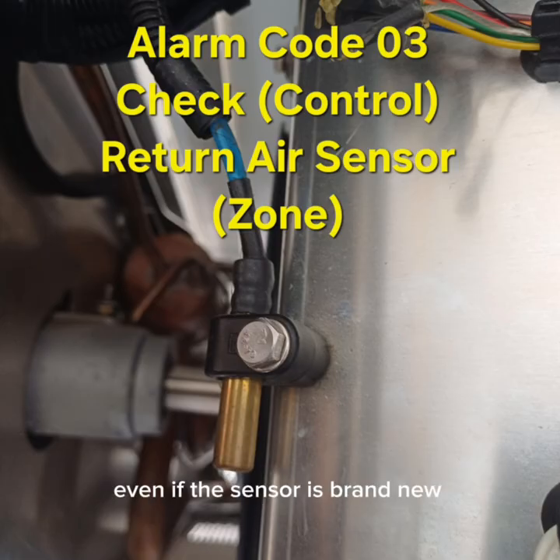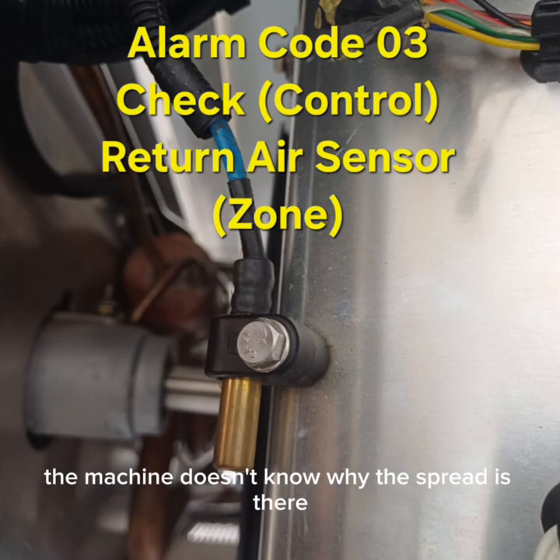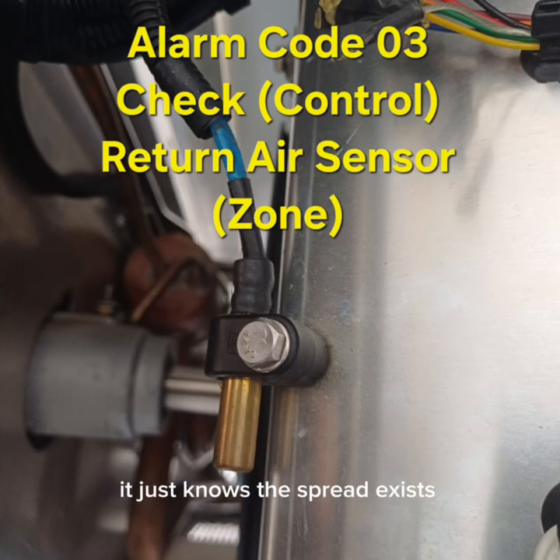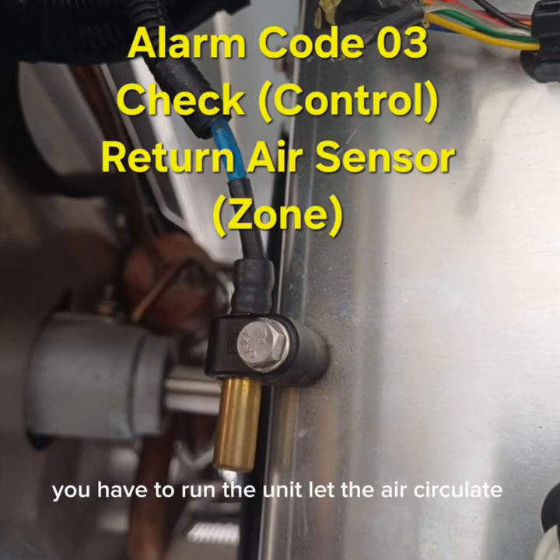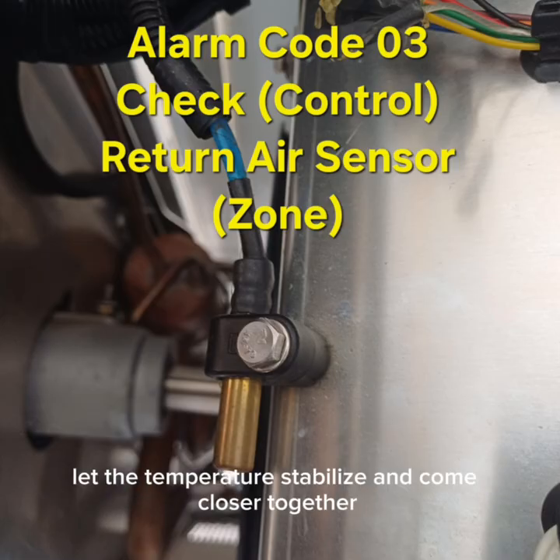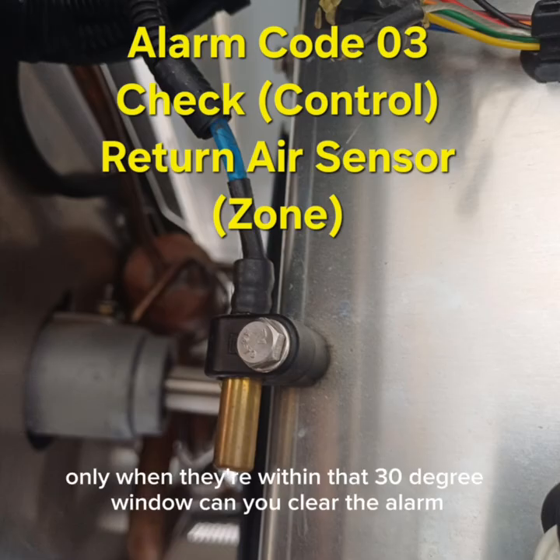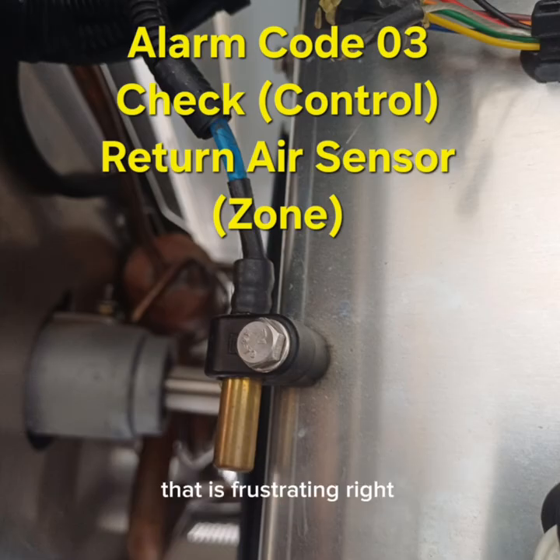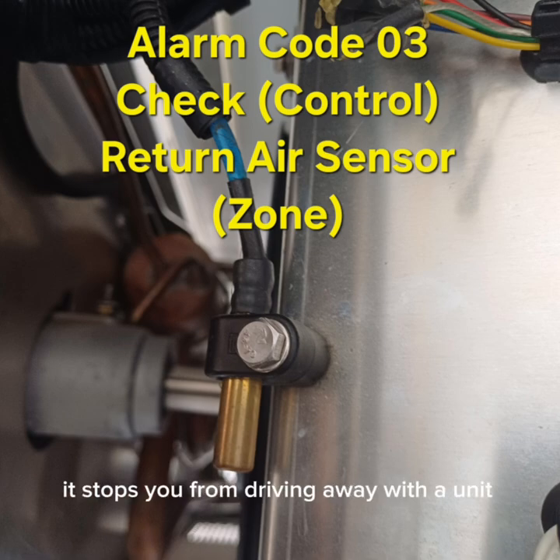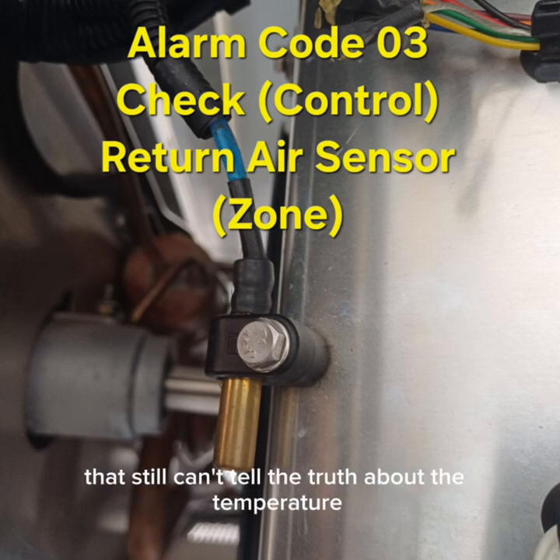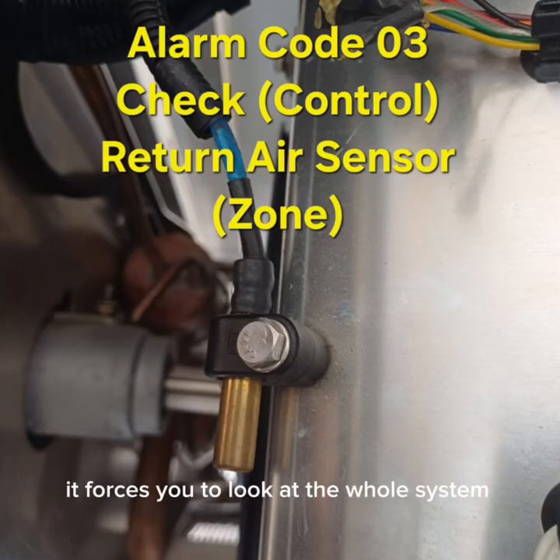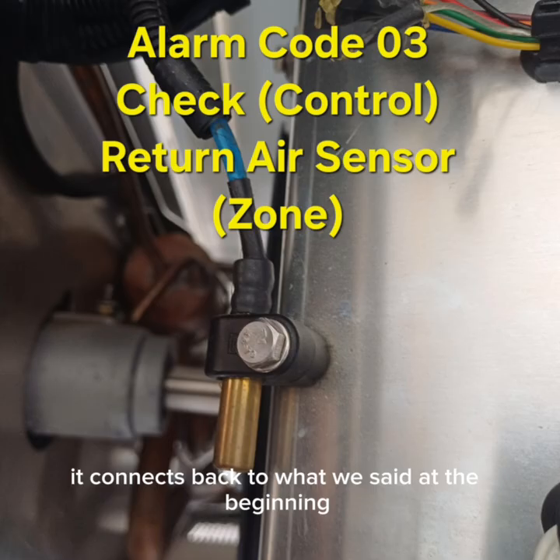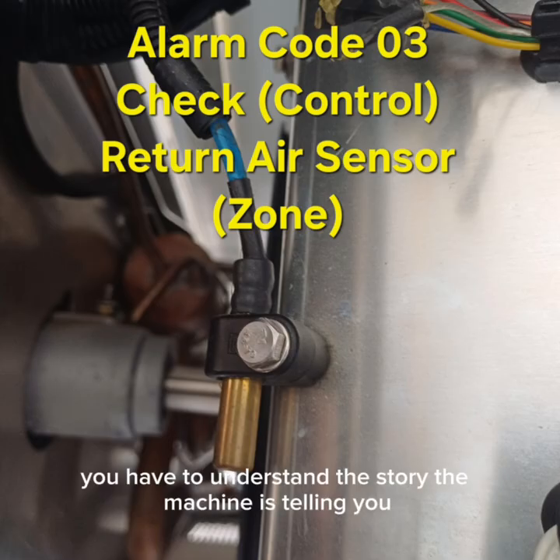Even if the sensor's brand new. Even if it's brand new, the machine doesn't know why the spread is there. It just knows the spread exists. So as a technician, you have to wait. You have to run the unit, let the air circulate, let the temperature stabilize and come closer together. Only when they're within that 30-degree window can you clear the alarm. That is frustrating. Right, but I get why it's necessary. It stops you from driving away with a unit that still can't tell the truth about the temperature. It forces you to look at the whole system, not just the one part you replaced. It connects back to what we said at the beginning. You have to understand the story the machine is telling you.